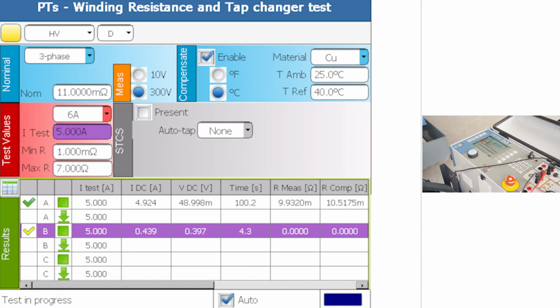The scenario is the same. The current slowly rises because it cannot rise in a step function on a winding. So right now the STS is generating about 2 amps, and the measured resistance of phase B is very close to the resistance of phase A. And in about 1 minute or something like that, we'll have the result.